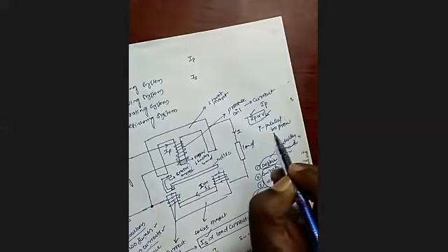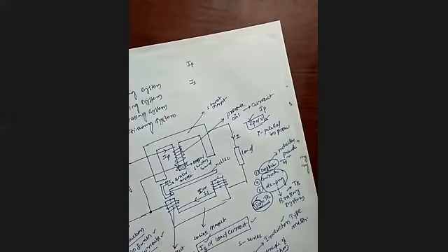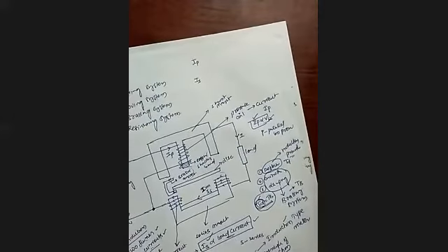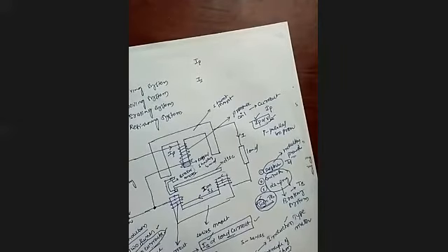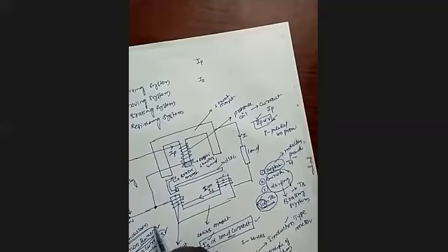Another current is called the current coil flux or series coil flux, represented by IS. This IS is proportional to the load current. For the production of a deflecting torque in an induction type energy meter, a machine requires two currents. Because of the two currents, two fluxes are developed. These two are very important.